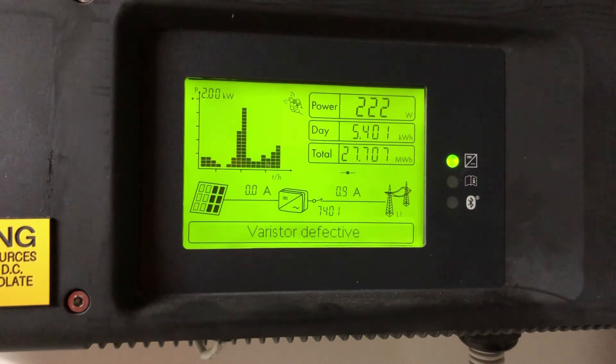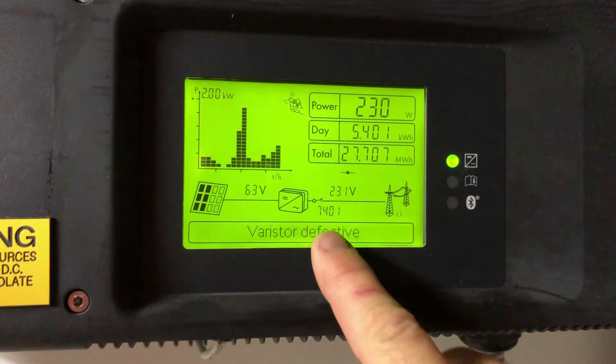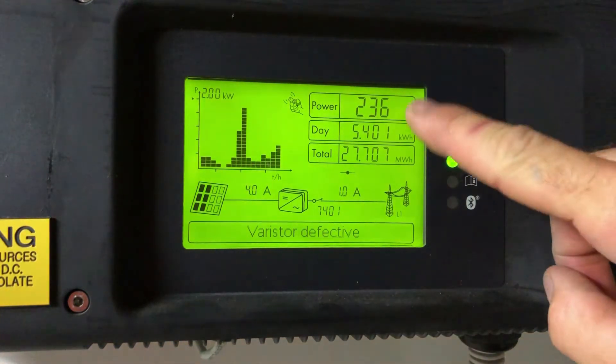Hi, Simon here from Gold Coast Solar Power Solutions. Today we have an SMA solar inverter, and you can see on the screen it says 'varistor defective' with a code 7401. The inverter is still working — it's still putting out power, 236 watts at this stage — but it's saying the varista is defective.